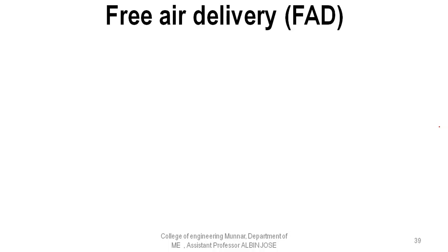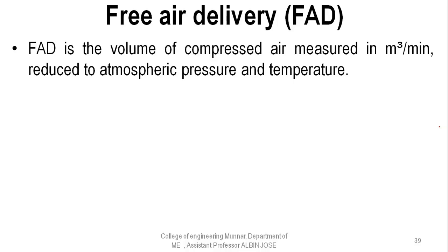Now we are discussing a term which is free air delivery, FAD. What is the FAD of a reciprocating compressor? Free air delivery is the volume of compressed air, measured in meter cube per minute, reduced to atmospheric pressure and temperature. It is the volume flow rate of compressed air reduced to atmospheric conditions, where the pressure and temperature should be at atmospheric conditions.